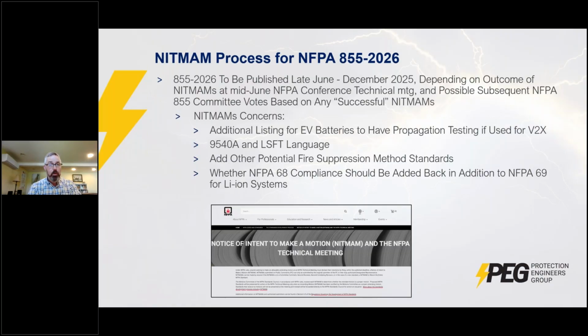Several of those address a new requirement for large-scale fire testing. We mentioned there's a 9540 listing requirement for the system for energy storage. There's a 9540A assessment of fire spread between cells, like thermal runaway propagation. And there's also now a requirement for explosion testing. That could be separate from 9540A. And now they're saying, even with those that we've used in the past, they're still seeing fires that were not predicted.